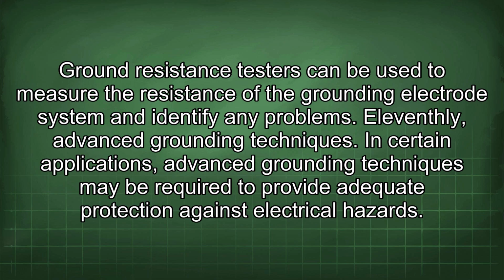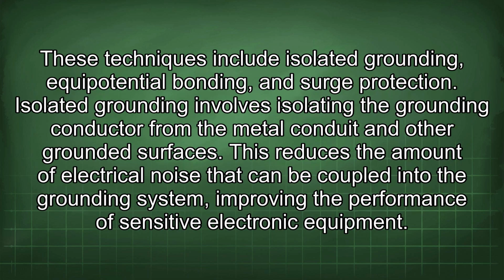11th, advanced grounding techniques. In certain applications, advanced grounding techniques may be required to provide adequate protection against electrical hazards. These techniques include isolated grounding, equipotential bonding, and surge protection. Isolated grounding involves isolating the grounding conductor from the metal conduit and other grounded surfaces.